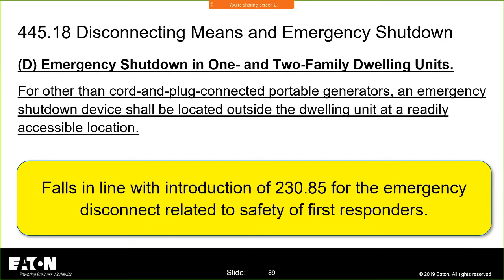Okay. And then finally in D for emergency shutdown, this is what aligns with what happened in 230. What you'll find is when you start showing the love to a section because of some reason, you start to clean up other areas in that section because people start to look at it with new eyes and go, we need to either clarify or fix some of the language here. But this was the prime intent in 445.18, emergency shutdown in one and two family dwelling units. Again, if it's a permanently connected type of generator and not cord and plug connected, you've got to be able to shut that thing down in a readily accessible location.